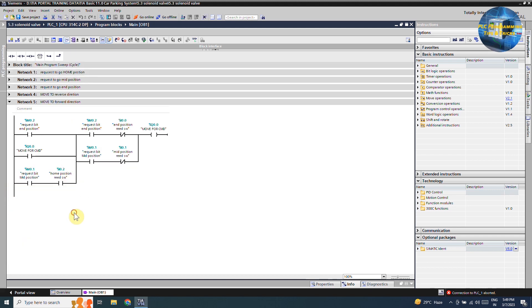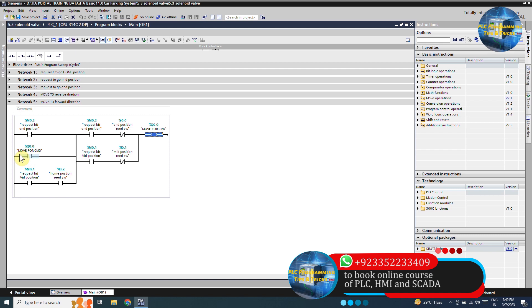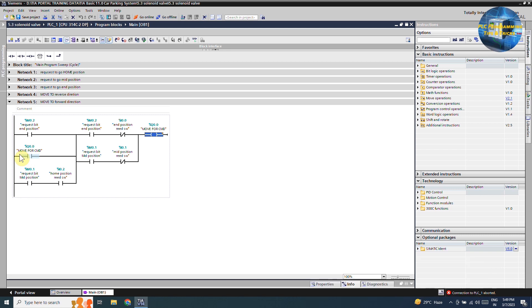In network 5, if the request to the end position m0.2 bit turns on and the cylinder piston is not at the end position sensor i0.0, it will latch on the cylinder forward command Q0.0 through its own normally open contact to turn on the forward coil. This way the cylinder will move towards the end position reed switch i0.0. As soon as the cylinder piston reaches the end position sensor i0.0, this normally closed contact will unlatch the forward command Q0.0.